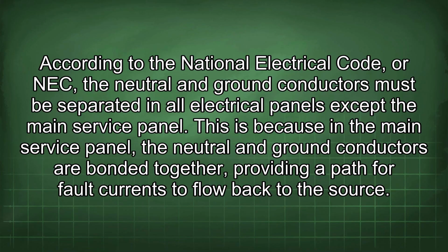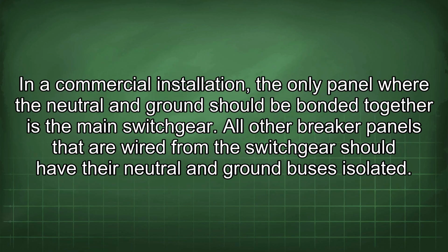According to the National Electrical Code, or NEC, the neutral and ground conductors must be separated in all electrical panels except the main service panel. This is because in the main service panel, the neutral and ground conductors are bonded together, providing a path for fault currents to flow back to the source. In a commercial installation, the only panel where the neutral and ground should be bonded together is the main switchgear. All other breaker panels that are wired from the switchgear should have the neutral and ground buses isolated.